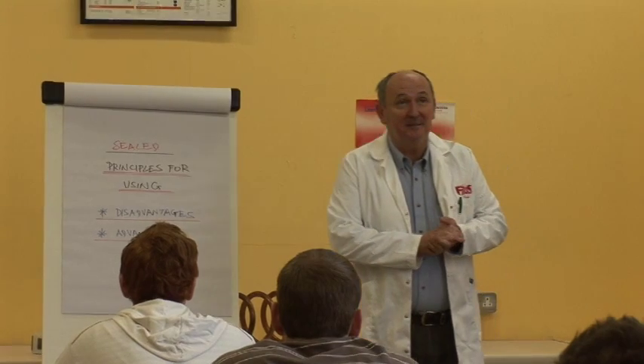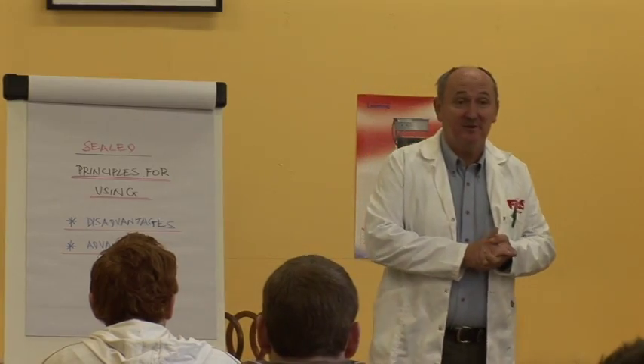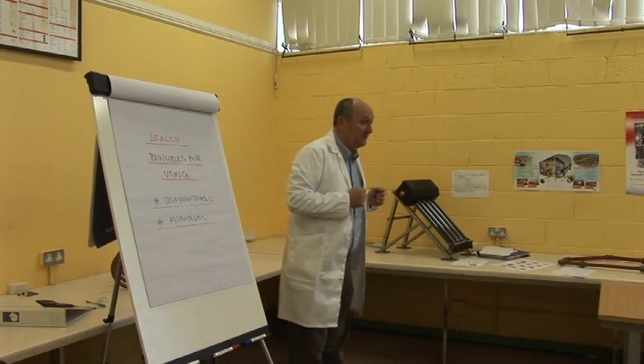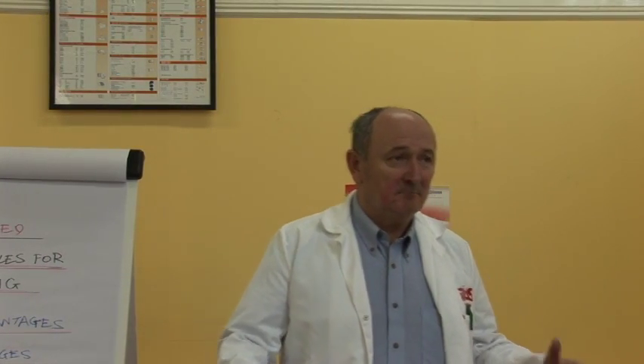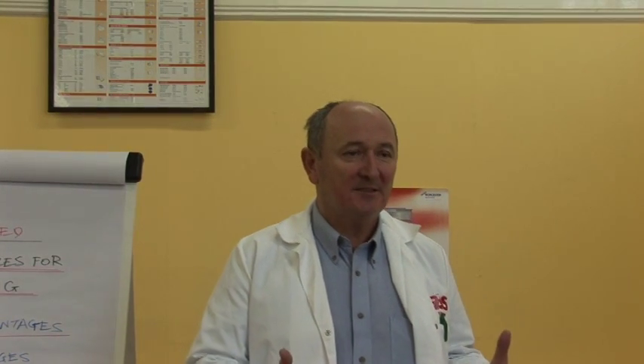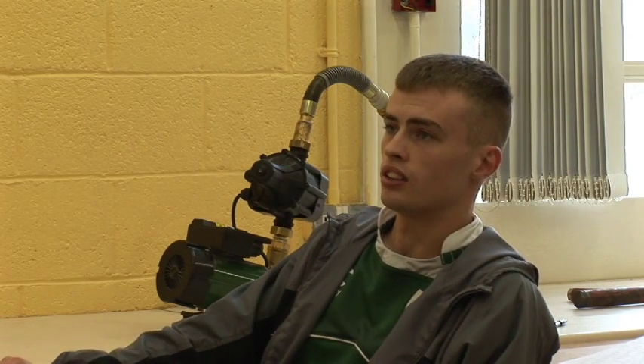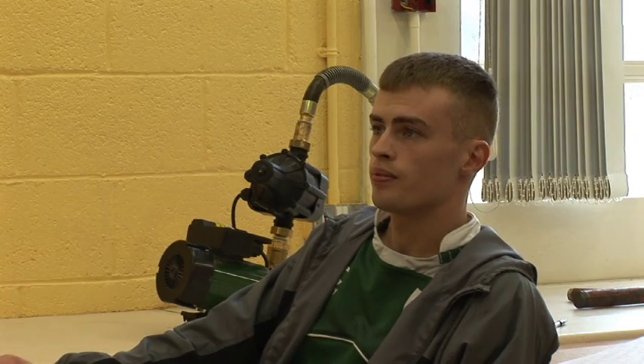We'll take all this on board in greater detail. Any questions on what I've spoken about? One question raised: sometimes when going into a house, the filler loops are still connected. If you've inherited that problem and your company hasn't done the previous work, you go in, do your repair work, fill the system to the required pressure, then disconnect and leave it that way. Regarding safety valves — the manufacturers set them at three bar.